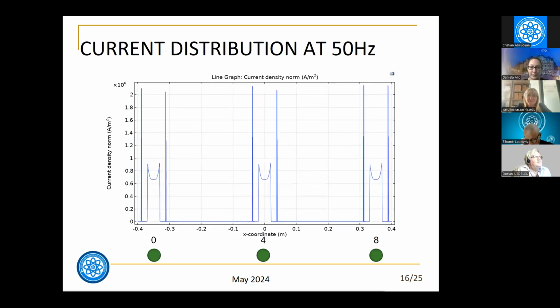This picture shows the current distribution in the middle line of all three cables. The central part is the aluminum part of the cable, and you can see that even at 50 Hertz, the proximity effect is visible. These other values are the induced current in the other two metallic layers in the construction of the cable.